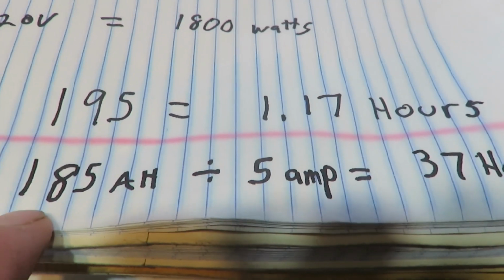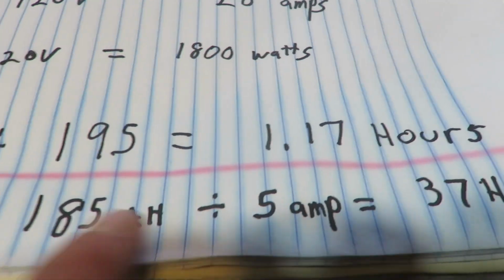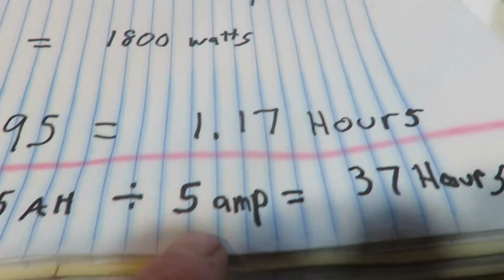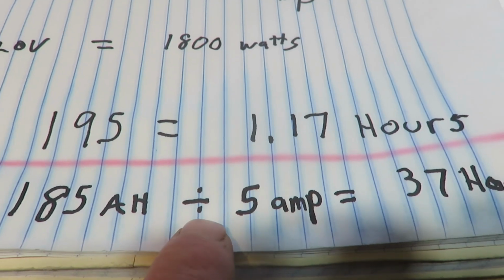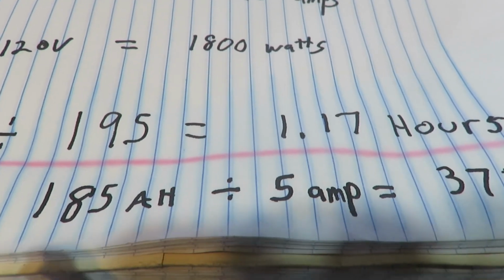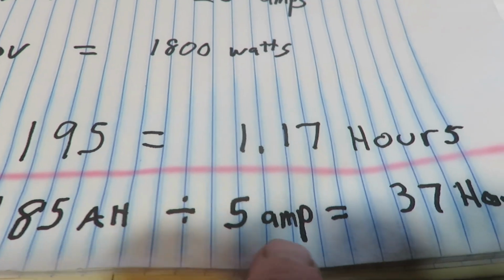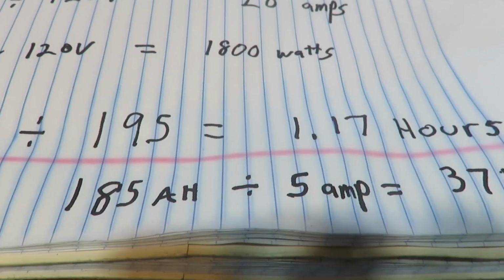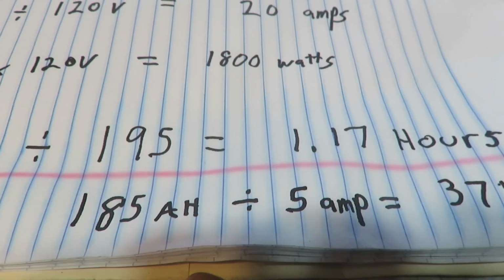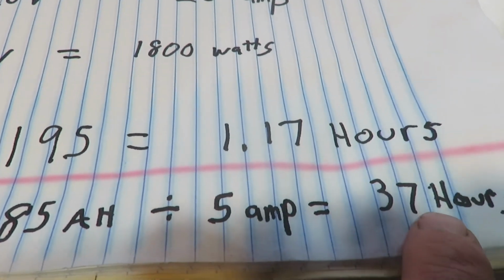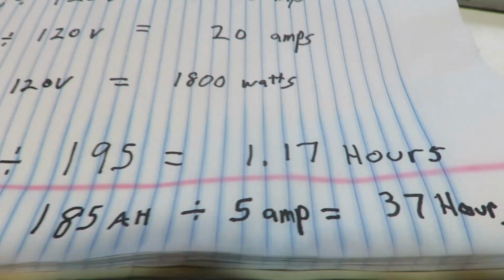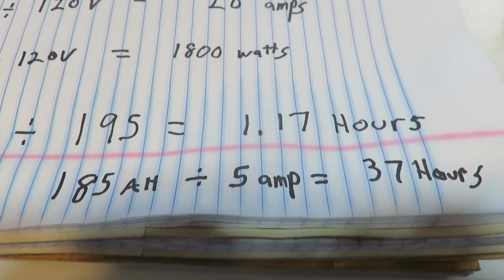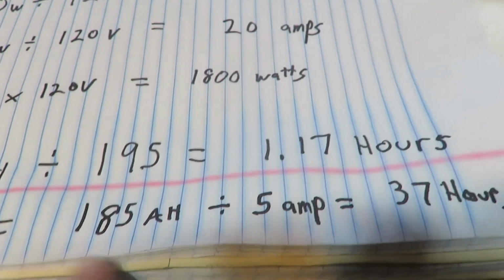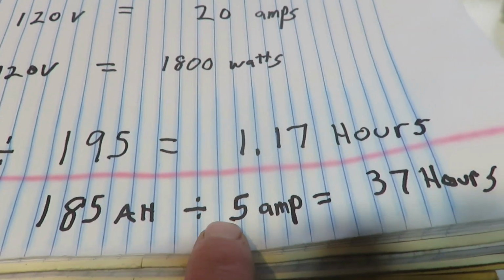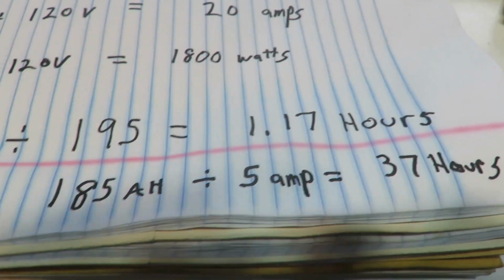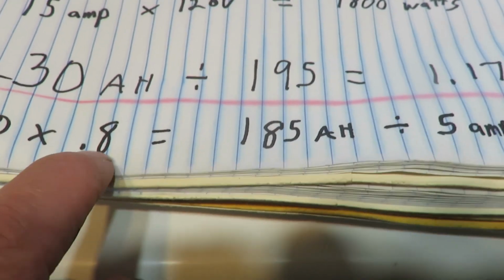So people ask how long it'll run a refrigerator or whatever. It could run it for quite a long time, but even with this number, you still need to factor in the inefficiency of the inverter, which might only be 90 or 95%, depending on what inverter you have. So you won't even get this many hours, because you're going to lose some of it in the inefficiency of the inverter. But that's pretty good. I mean, you should be able to run a pretty good load for a whole day on that one charge, if you wanted to take it down all the way to 20%.